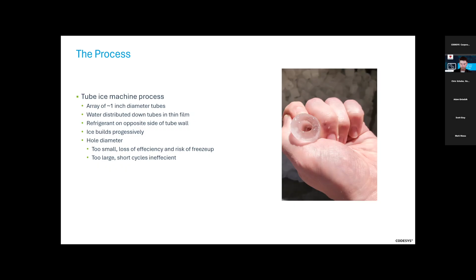We freeze the water, which builds the ice up in those tubes, and then the way that we get the ice out of there is with a thing called a hot gas defrost. So in that process, we're always putting the cold liquid into these tubes to freeze the water, and then we flip the machine into what we call a harvest. And at that point, we inject the hot gas from the refrigeration cycle right into the machine. It warms the tubes up, and all those tubes fall. And when they're falling, there is a cutter on the bottom that is spinning, and it's sizing them into these little inch and a half long pieces. And that harvest process will take about 2 minutes, and then we'll return back to a freezing cycle. And we have a lot of little steps in between there to balance some things out, but that's the gist of it.